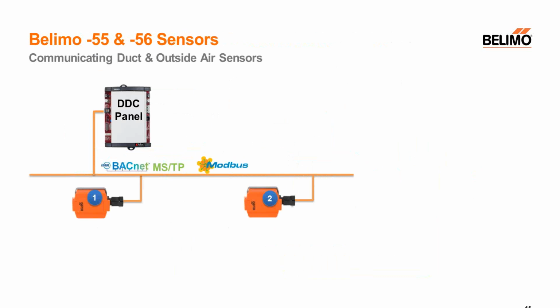I mentioned communicating sensors. We have a line of duct and outside air sensors that have BACnet MSTP or Modbus communication. On the Dash Mod actuators, it's software selectable. So basically you plug a handheld into the actuator, you can address it, you can change the protocol, you can change the speed, things like that.